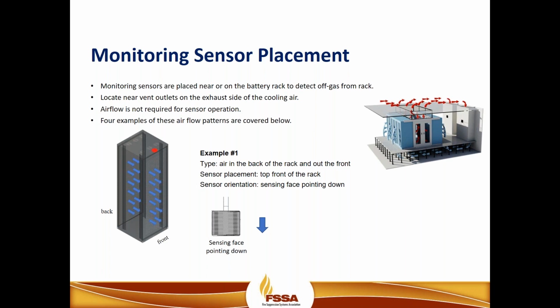Where do we place these sensors? Again, going back to what we know from high airflow environments, mission critical type facilities doing smoke detection, we want to place the sensors in the path of airflow. So if you're cooling from the back to the front, you want to place the sensor in the front and in the top of the unit.